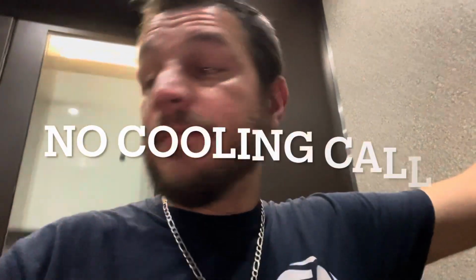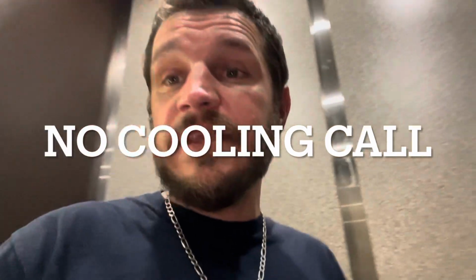All right, we got a no cooling call. I had already been up there and checked the thermostat. There's no 24 volts at the thermostat, so I checked the breakers in that space. Nothing was tripped, and I know this unit up here is an RTU, so I'm getting the key for that space.